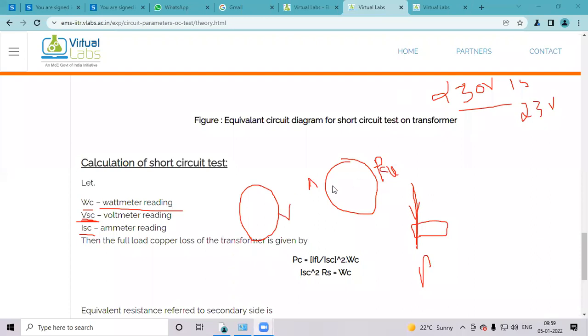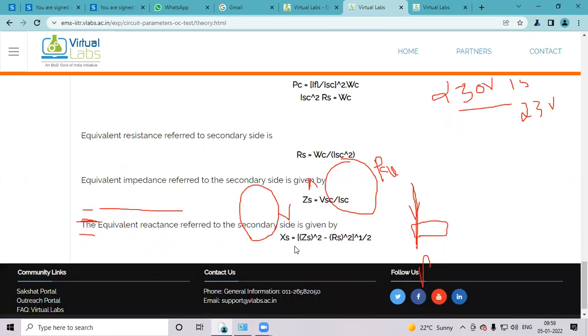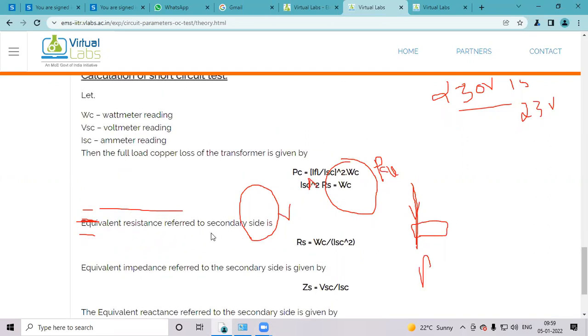So according to this we are finding the full load copper loss PCU, which is nothing but WC. After that we calculate the equivalent resistance referred to the secondary side, that is equivalent resistance RS, which is WC divided by ISC square. ISC is the current flowing through the secondary side, the short circuit current.